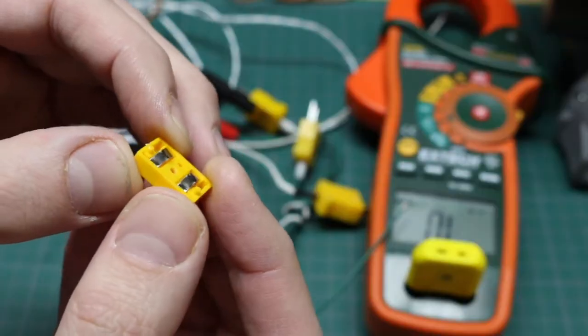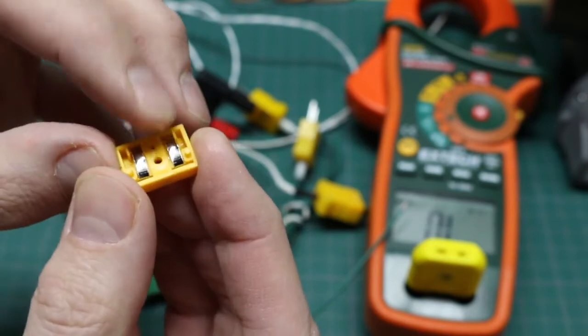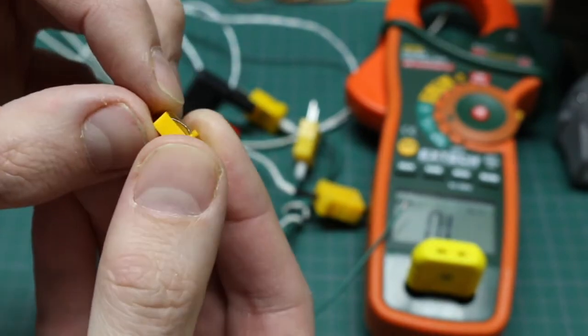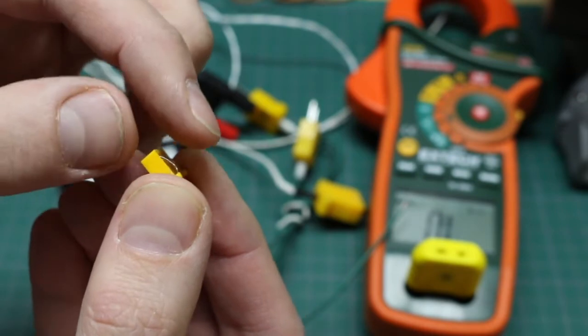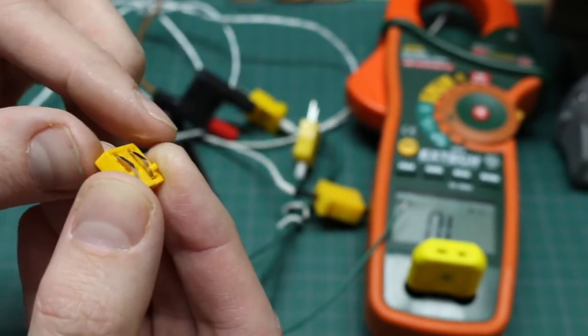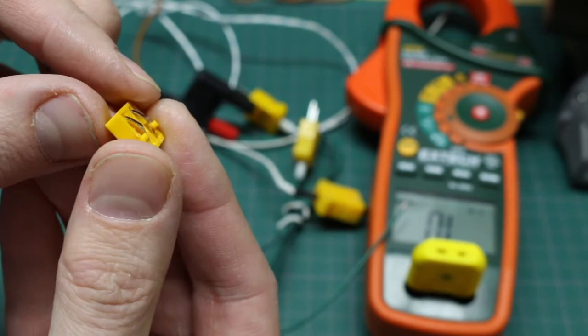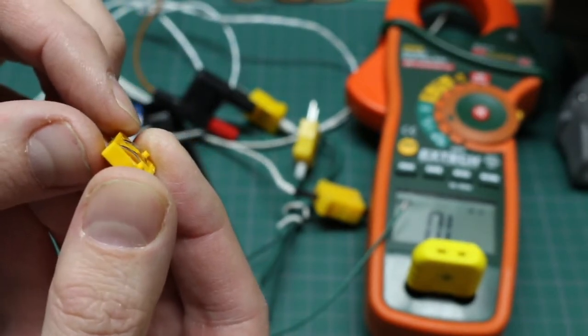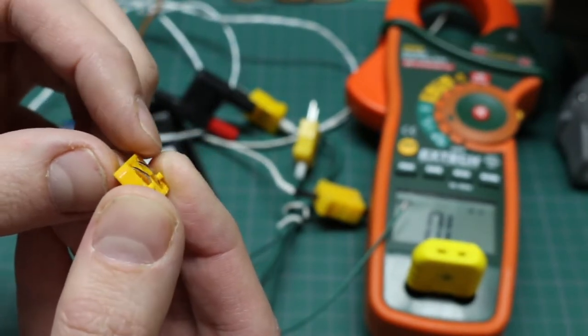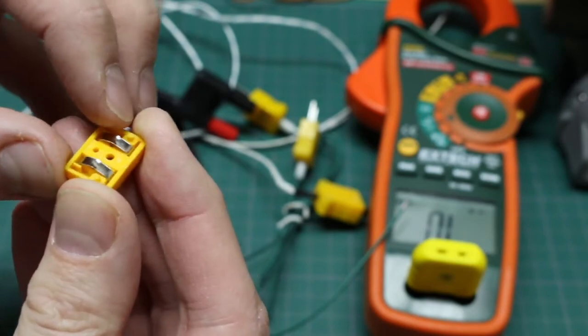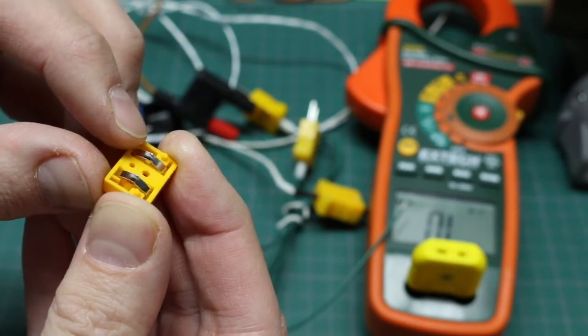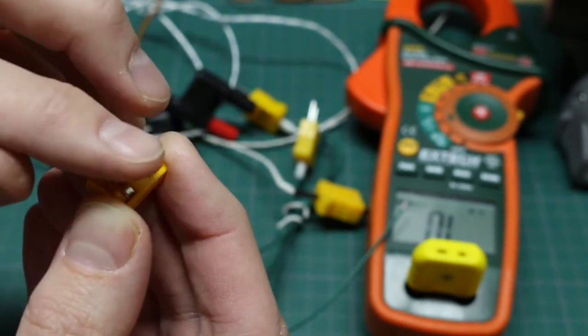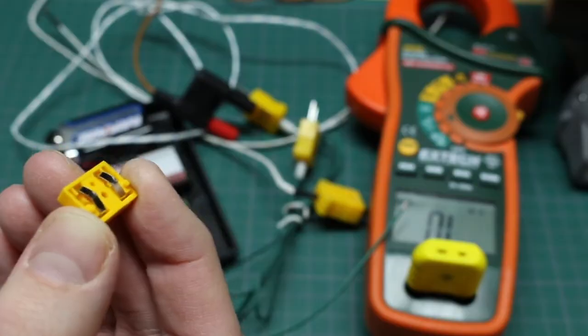This is the other side of the connector where the tabs help make contact with the probe. Here they are bowed out to help push down and make contact when the probe slides in, but those were very flat. One was a little curved looking intentionally to make contact, the other was really flat. So I just pulled these out and bent them more exaggerated and I'm going to put it back together and it should have enough tension on there.